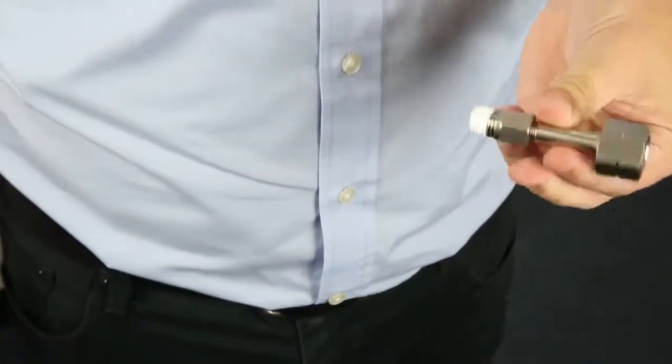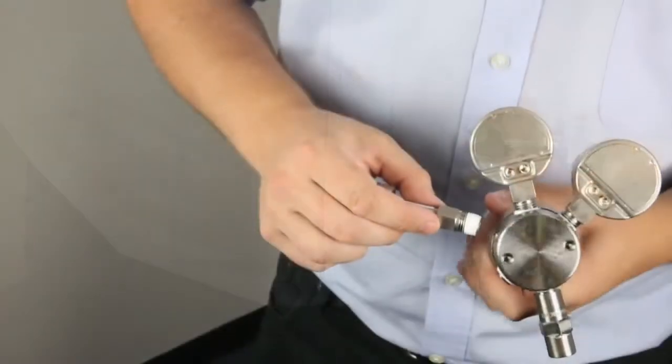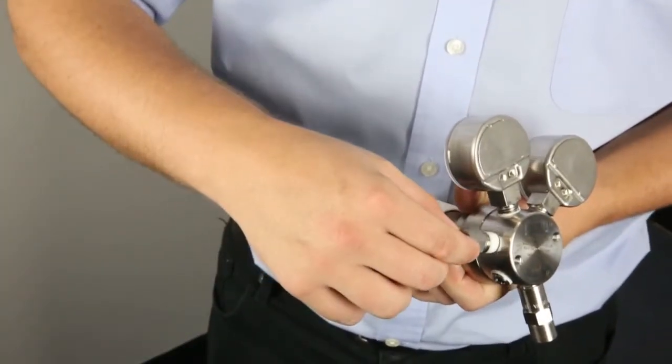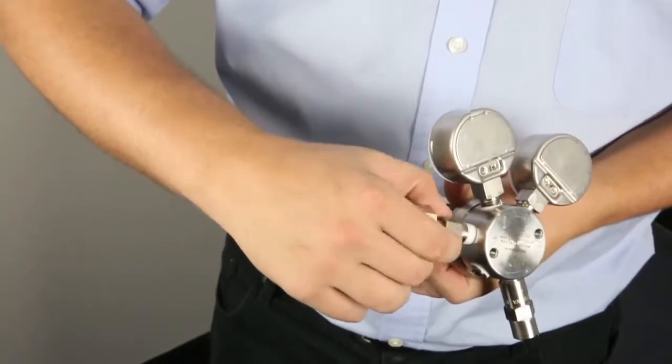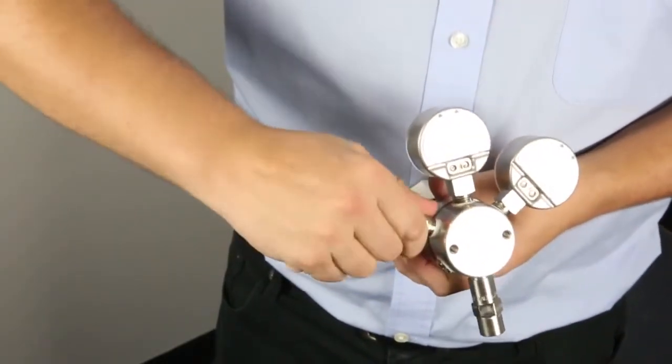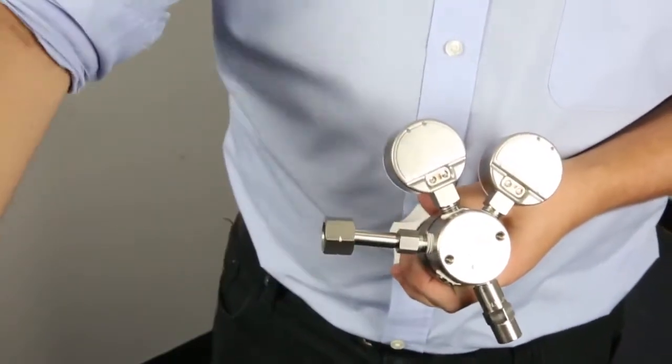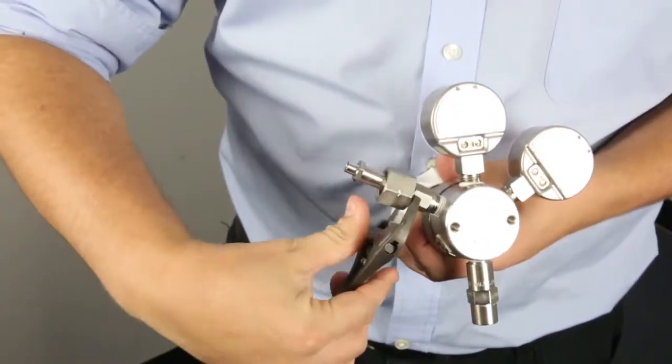When taping the thread of a cylinder connector it is important to remember a few key points. Firstly, make sure the tape starts at the first thread and does not come over the end of the connector. Also the entire thread doesn't need to be taped, it should generally not go beyond three quarters of the thread.